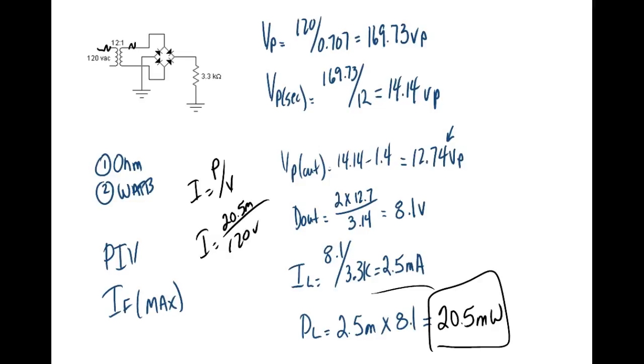Fuses are not sized for peak, they're not sized for peak to peak. They're sized for the effective voltage, right? Because that's what your load sees. Your load does not see peak or peak to peak, it sees the effective voltage. And this would be I of the load - I mean, this would be I of the primary right there. So y'all see how we did that?